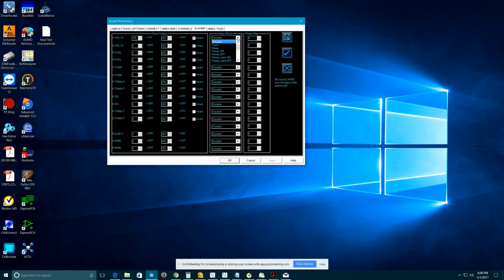Then you set up the action that's going to happen as a result. As far as the unit itself, it can simply alert via a common alarm output, or turn a relay off. In this case, it can turn a latching relay on and off, and actually add another analog output - so if one input goes over temperature, you want it to turn something else off, or set a voltage output on another system, you can assign those. That's handled by the unit itself. So this would be a closed-loop system where you don't have internet connectivity for these actions to occur.